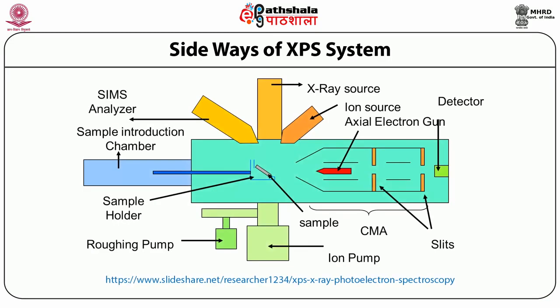A slide shows a side view of XPS where the position of the parts of XPS can be seen. The sample is introduced through a chamber in contact with the outside environment. It will be closed and pumped to low vacuum. After the first chamber is at low vacuum, the sample is introduced into the second chamber in which a UHV environment exists.